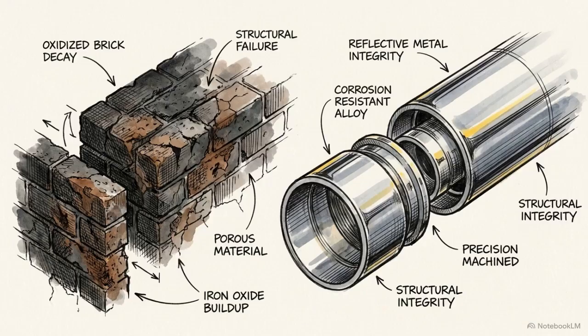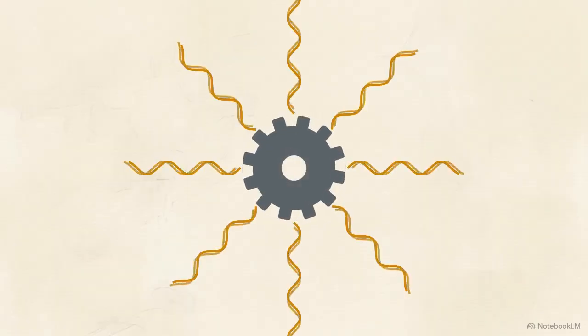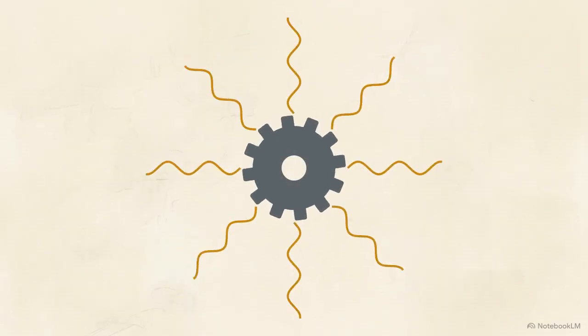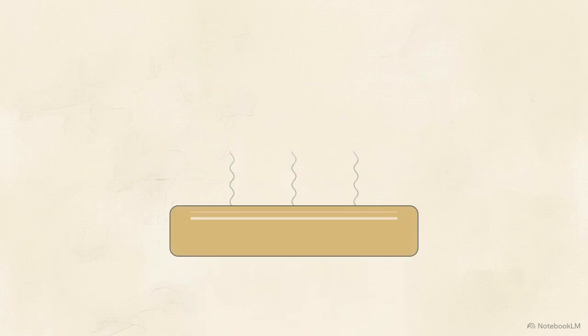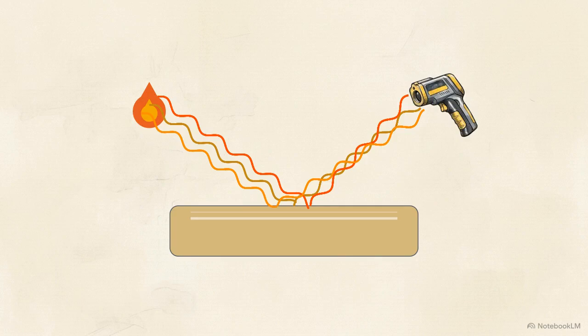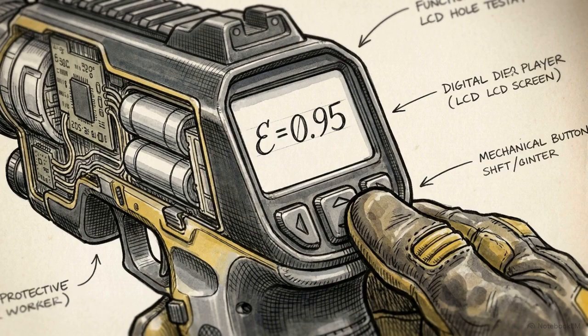But real-world objects do not emit thermal energy with perfect mathematical efficiency. This physical deviation is measured as emissivity. Oxidized metals and organic materials have high emissivity, effectively radiating their own internal heat. Shiny, polished metals have incredibly low emissivity. Instead of emitting their own temperature, they act like thermal mirrors, reflecting the infrared energy of the machinery operating around them. To correct for this, the MX6 allows technicians to manually adjust the emissivity baseline in precise 0.01 increments.